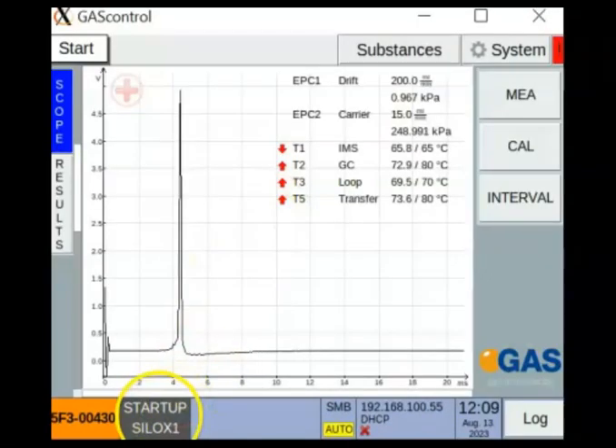And we are in the SILOX startup phase. We have a high drift gas flow and we have 15 milliliters carrier gas flow. We already see that the reaction ion peak is quite clean. Maybe after transport or after the fresh installation we can have a bumpy reaction ion peak, and it will need to go through a cleaning phase.